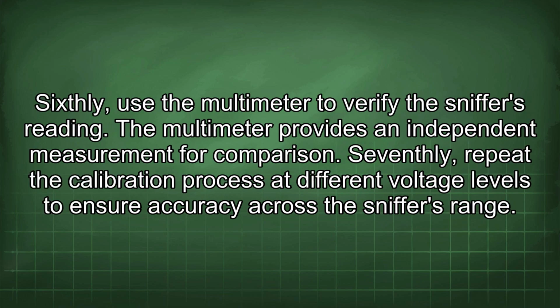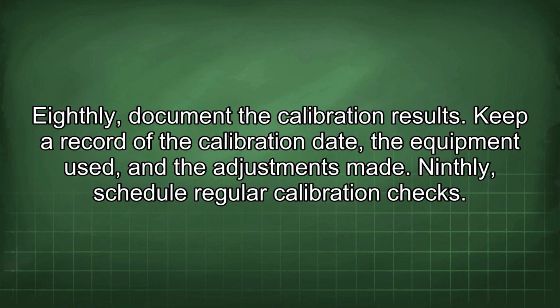Sixthly, use the multimeter to verify the sniffer's reading. The multimeter provides an independent measurement for comparison. Seventhly, repeat the calibration process at different voltage levels to ensure accuracy across the sniffer's range. Eighthly, document the calibration results. Keep a record of the calibration date, the equipment used, and the adjustments made.